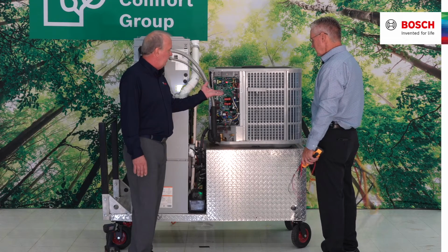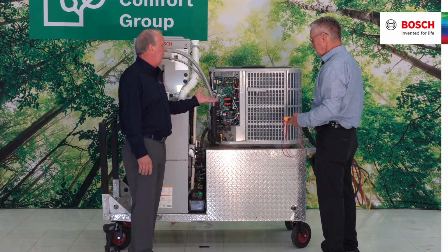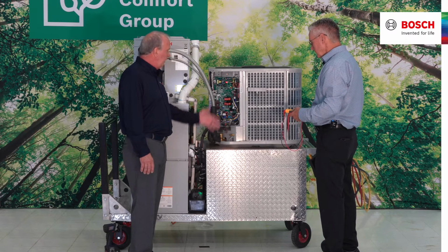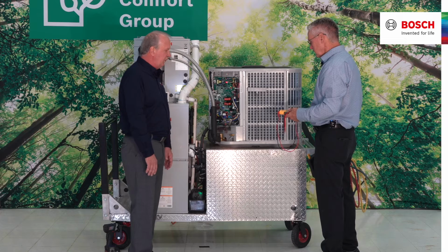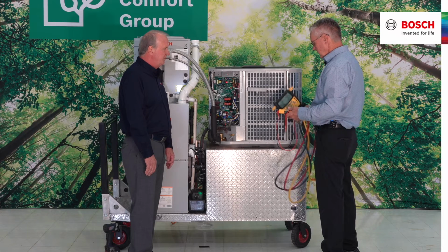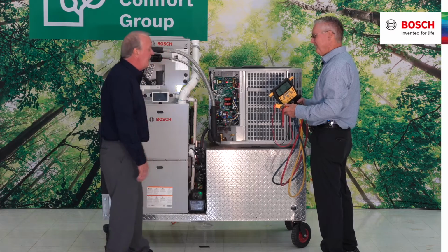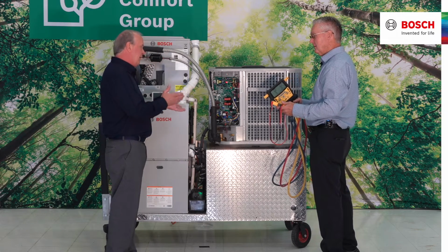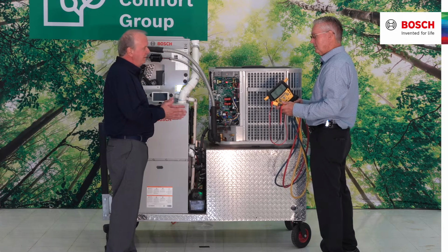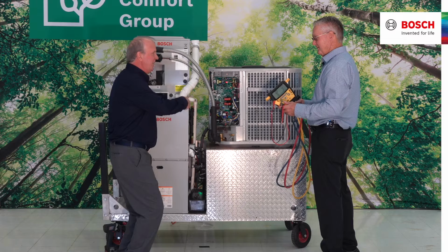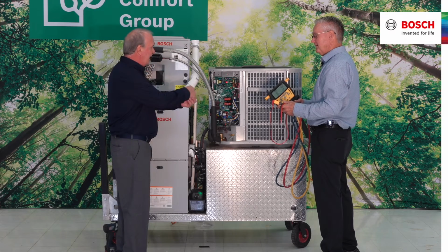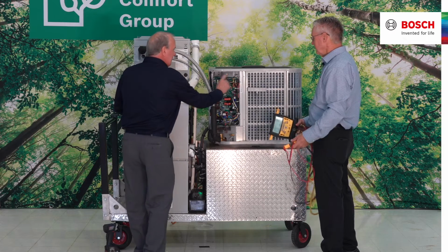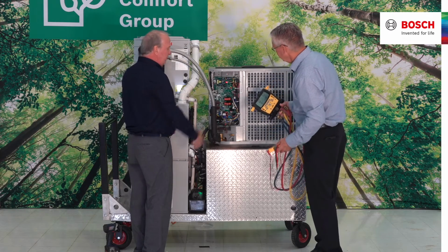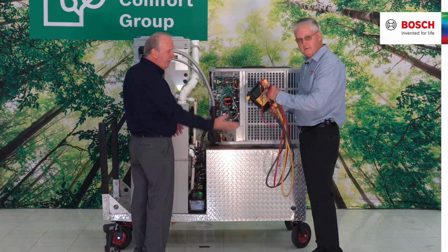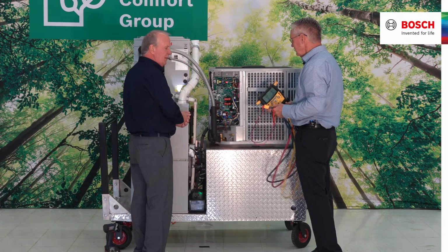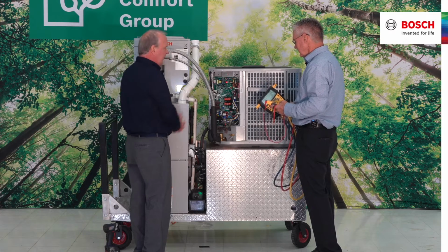This system comes with 25 different system parameters built into the board that will give me all the information that the tools in your hand will give us. But these cost a lot of money. Well, I'm sorry. You can use them on someone else's equipment, but on ours, I always say a 5-gallon bucket and a 1/4-inch nut driver. You need a bucket to sit on, a nut driver to take the door off, and then you just scroll through the parameters and I can get my high side, my low side, my superheat, my line 1, line 2, my amp draw, my compressor voltage, my DC voltage to my compressor, all built within the parameters of the board.